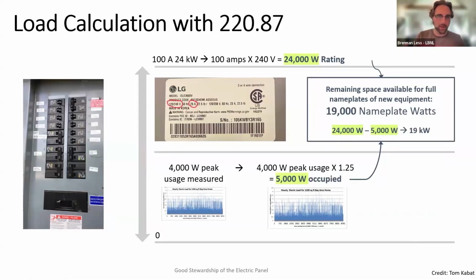This is just a quick illustration of the calculation. You might have metering data. Let's say you had a peak demand of 4 kilowatts. You multiply that by 1.25, that gives you 5 kilowatts. And if you had a 100-amp panel that has a 24-kilowatt rating at 240 volts, subtract those two, you can add 19 kilowatts of new loads. So you can add a new cooking range or an HVAC heat pump, lots of capacity there. So that's sort of how that code section works. Let's jump to the next slide.